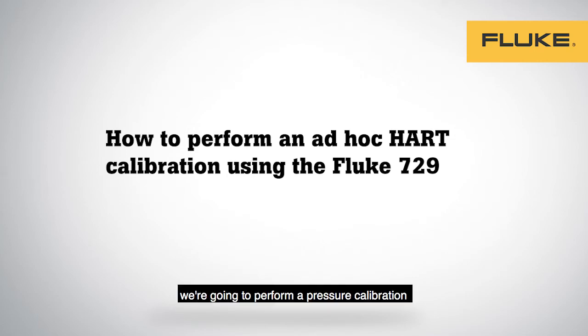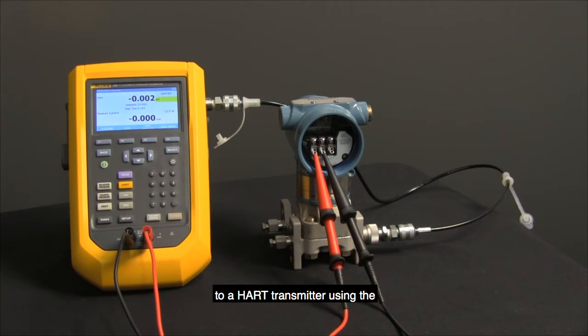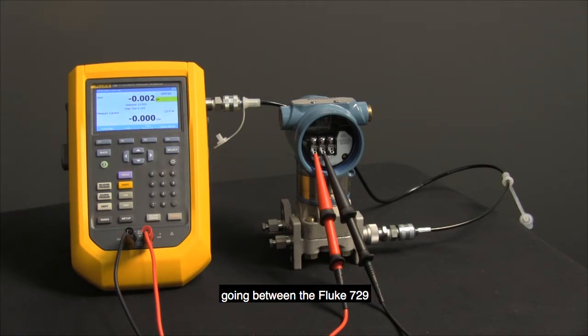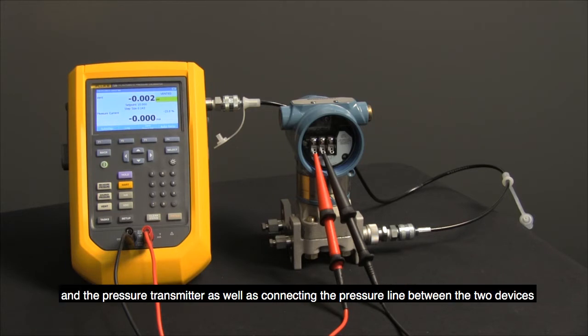In this video, we're going to perform a pressure calibration to a HART transmitter using the Fluke 729 automatic pressure calibrator. To get things connected up, you've got your 4 to 20 milliamp jacks going between the Fluke 729 and the pressure transmitter, as well as connecting the pressure line between the two devices.